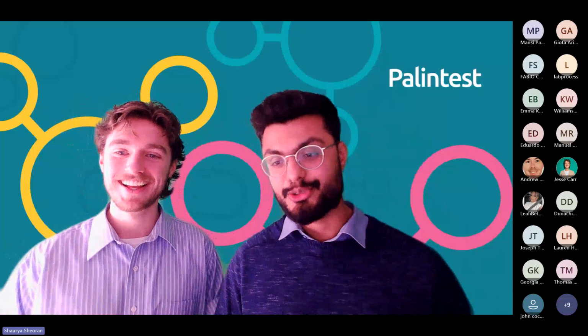Andrew has asked how often should I get my instrument serviced by an authorized service center? That's a good question, Andrew. These instruments are performing a really crucial job. They are used in regulated environments, and it's really important to make sure they are calibrated, because they're testing sometimes very sensitive levels of chemicals in water. Hence, we recommend annual calibration. That is the best practice to make sure you are getting the most accurate results. We have our headquarters in the UK, but also we want to expand to a global service network. We have some authorized service partners across many countries operating now, and we plan to continue to expand our footprint to make sure our customers receive the best service.